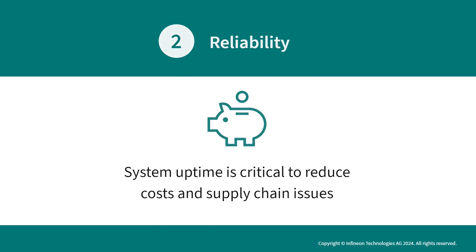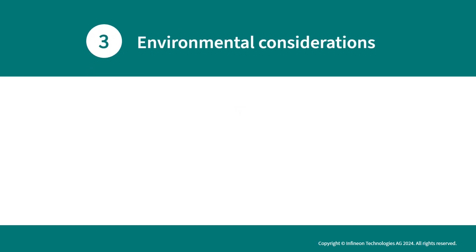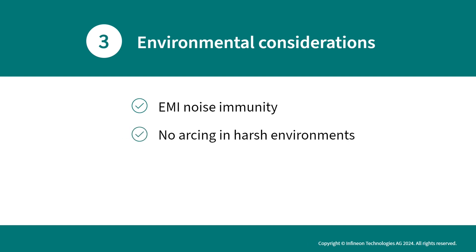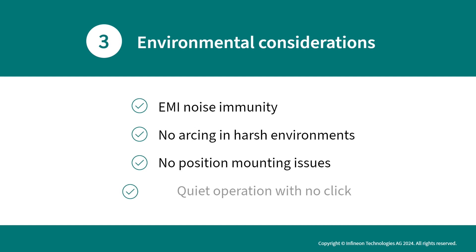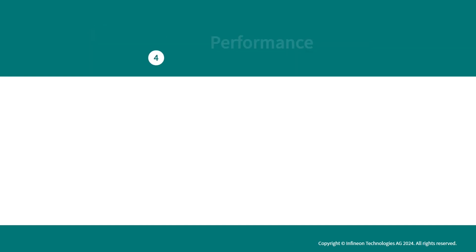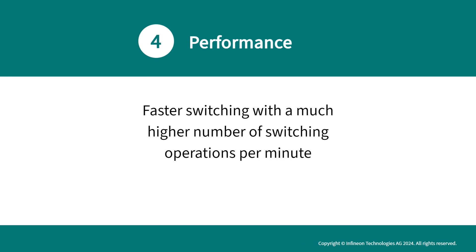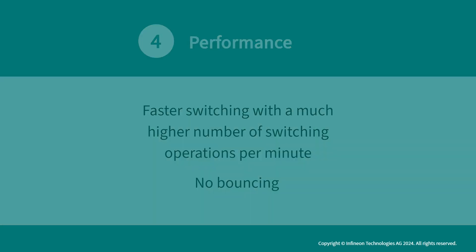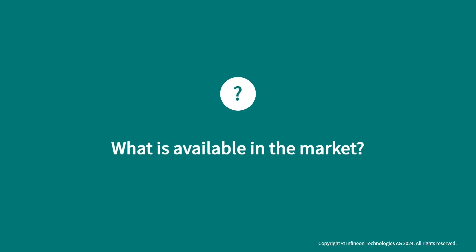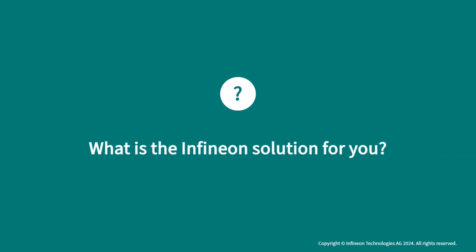Third, for environmental considerations, solid state relays offer EMI noise immunity, no arcing in harsh environments, no position mounting issues, and quiet operation with no click. Fourth, in regard to performance, SSRs show faster switching with a much higher number of switching operations per minute, a longer lifespan, and no contact bouncing.